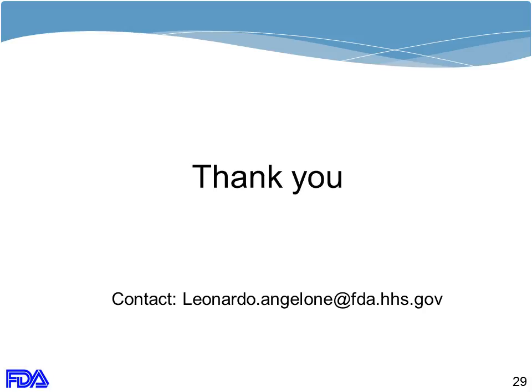Yeah, and thank you for the question. It allows me to clarify. What I mentioned is that there is no current standard for safety of patients with active implanted medical devices undergoing MRI. So it was a very specific section, and we're talking about safety of patients. The active implants are devices like deep brain stimulators, pacemakers, cochlear implants. And the standards I was referring to were specifically for safety of patients with such implants undergoing MRI. We're not talking about standards in general about active implants or patients with implanted devices.